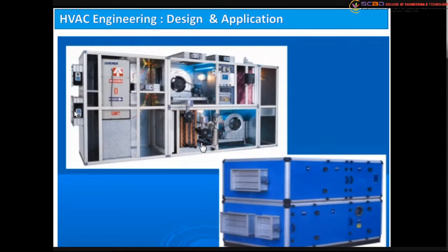See, this is the air which comes from the outside, goes through the filter section, then goes through the cooling coils. This is the cooling coil. You can see the copper brown color, which is the cooling coil. This will be the chilled water which will be supplied to the cooling coil.